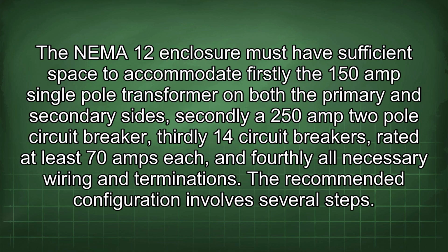The NEMA 12 enclosure must have sufficient space to accommodate firstly the 150 amp single-pole transformer on both the primary and secondary sides, secondly a 250 amp 2-pole circuit breaker, thirdly 14 circuit breakers rated at least 70 amps each, and fourthly all necessary wiring and terminations.